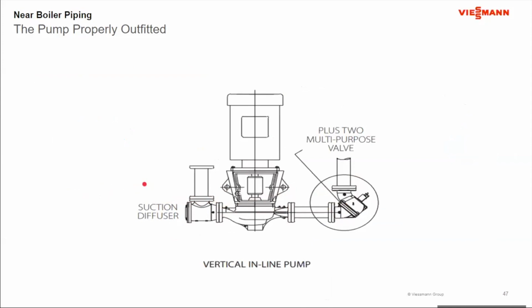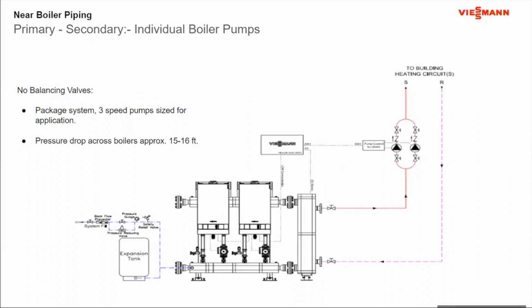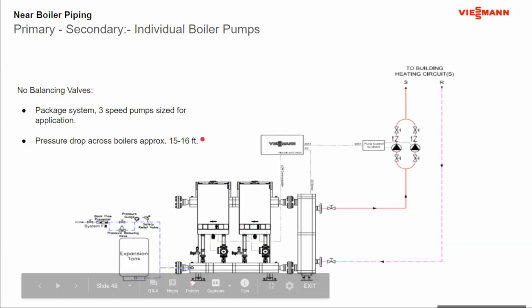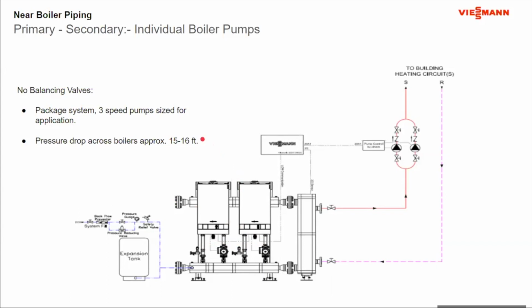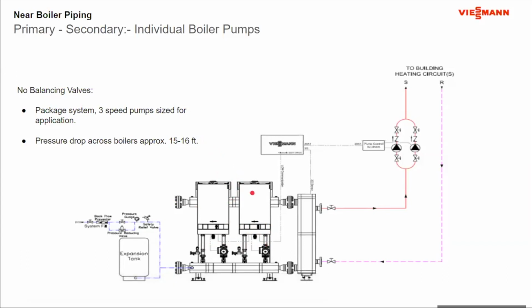Now, I will say there is one exception. My one exception is back to the manifold system when I start to do the low mass wall mounted water tube boilers, and you won't find balancing valves in here. Why not? Well, first off, in most cases, the pressure drop across the boiler alone is going to be in that 15 to 16 feet range, which brings it up to where it should be on the pump curve. And from an aspect of packaging, the pump is usually sized properly for the system. So all it needs is a check valve and an isolation valve, and there's no balancing valve in this kind of application. So this does become the exception to the rule when we start to look at the need for the multi-purpose valve. I need a check valve, I need an isolation valve.